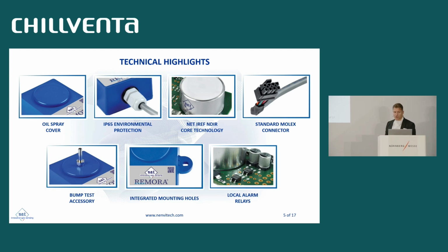The design of the sensor has been centered around the applicable standards in the market. It features an oil spray cover that is designed to pass oil spray tests, which are a requirement of the future standards for refrigerant sensors in applications for refrigeration and air conditioning. It is available with IP65 certified environmental protection to guarantee resistance against humid or aggressive environments.